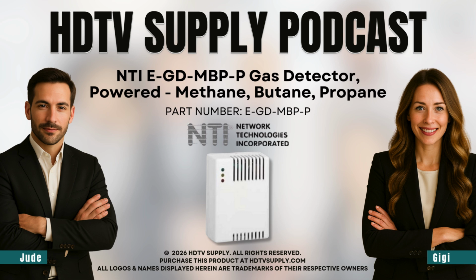Okay, so its primary job is continuous air monitoring. It's sniffing for the big four combustible gases: methane, propane, butane, and acetylene. And if it finds them, believe me, you're going to know about it. You certainly are. The audible alarm is specified at 94 decibels at a distance of 1 foot. And to put that in perspective for you, 94 dBA is louder than an average lawnmower. It's really designed to cut through the ambient noise of a busy data center or some other industrial space.